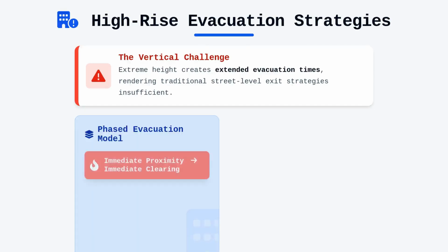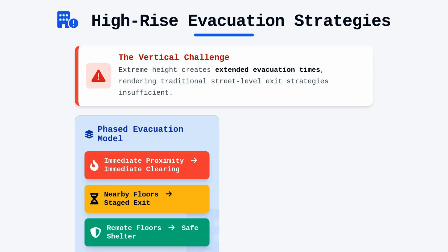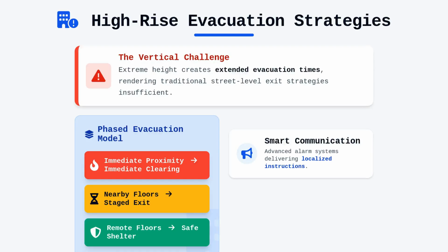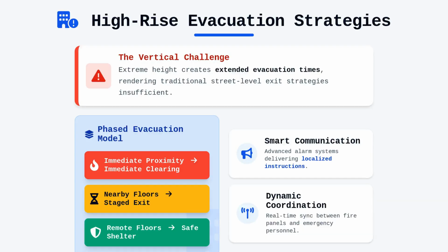Instead, we see the implementation of phased evacuation, where floors in immediate proximity to the fire participate in the clearing process while others safely shelter until directed otherwise. This strategy necessitates sophisticated fire alarm and communication systems that can provide clear, localized instructions. Furthermore, the use of elevators for occupant egress is no longer a purely theoretical debate. It is an integrated engineering reality that requires rigorous redundancy in power supplies, water protection for shafts, and lobby pressurization to ensure those shafts remain tenable for the duration of the event.